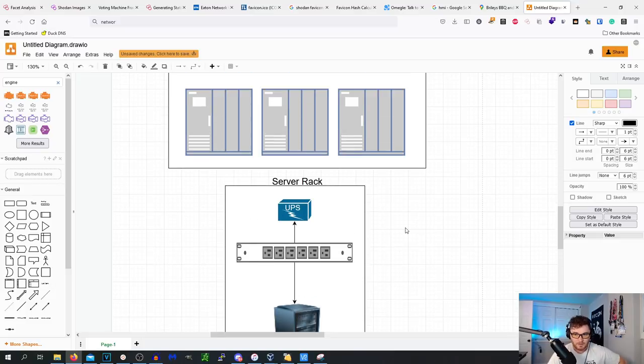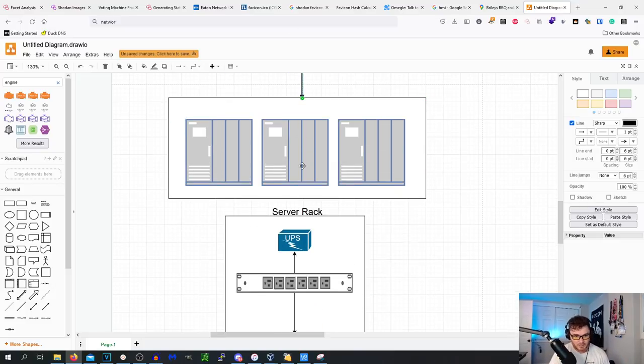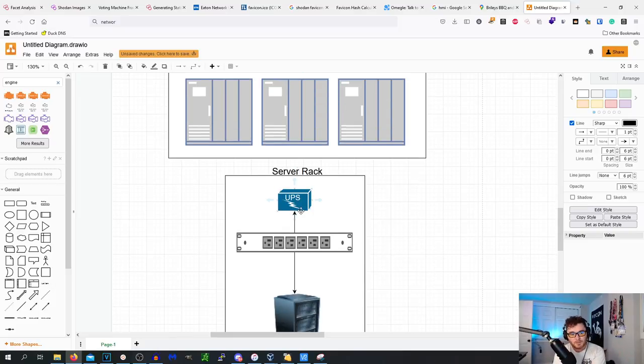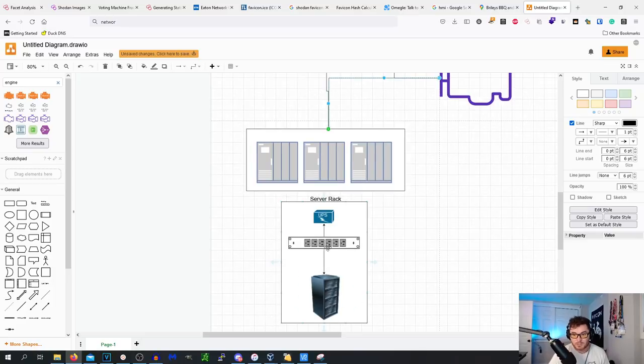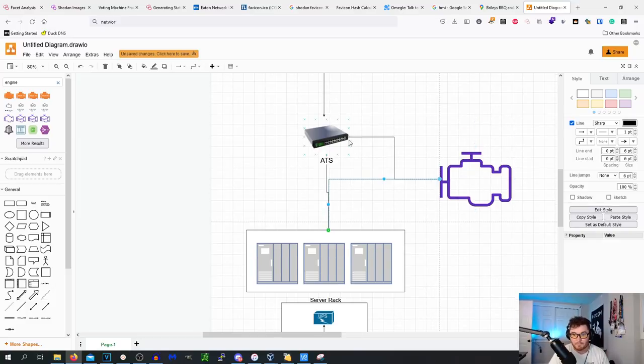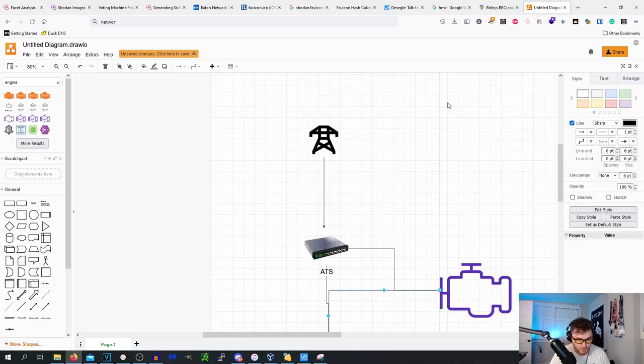Now, the single points of failure are not in the UPS room, because there are going to be multiple UPSs in there, but the power line going from the UPS room or PDU room to the actual UPS in the server rack. Obviously, some data centers will have two UPSs and two PDUs. You saw a little bit ago that I had a picture of PDUs, and there were two of them. Those are on two separate circuits. So in a true N+1, you'd have that one server, and multiples of these, multiples of these, and if you can, multiples of those.